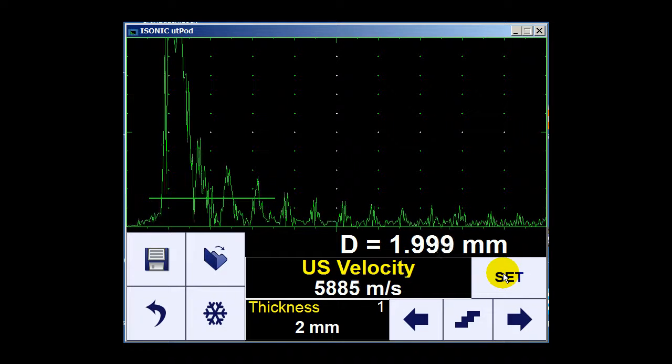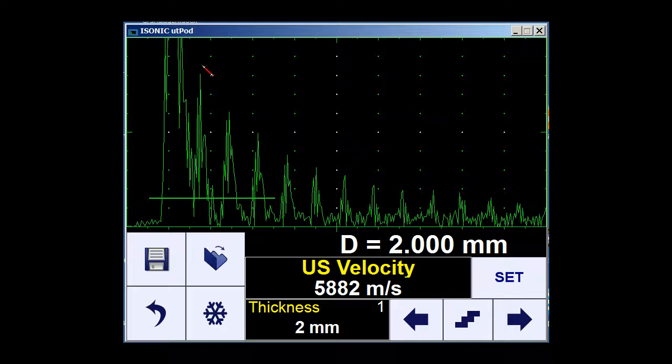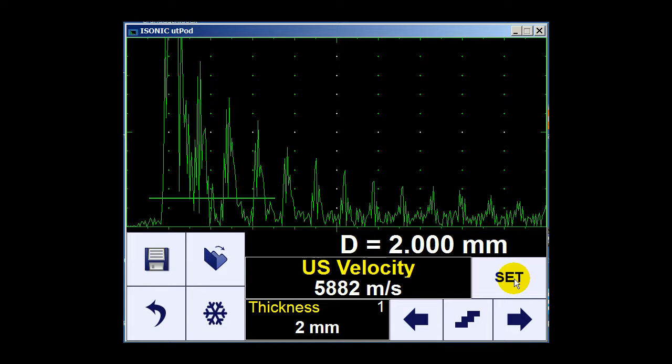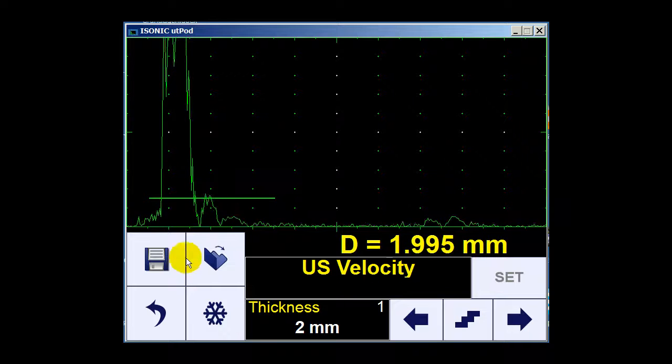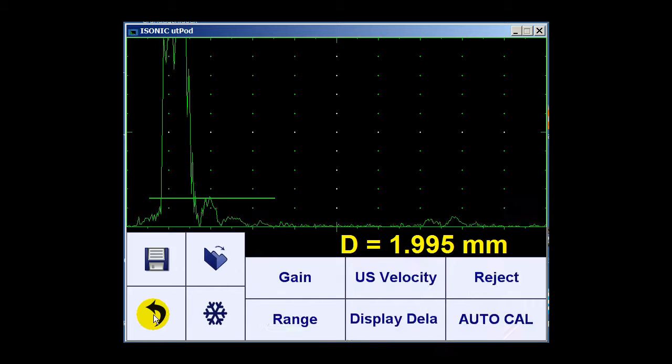And then if it is all properly set, the echo is between 80 to 100%, I just press the set button. Now the system is set for measurement on this material. So I can go back and go to the measurement mode and I will perform my measurements.